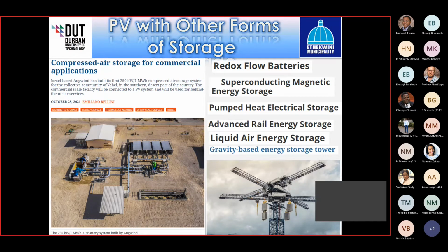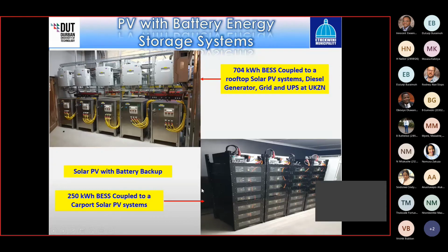And there are gravity-based energy storage towers, which use electricity to raise up weights. And when electricity is required, it then lowers these weights and generates electricity. So there are multiple energy storage forms and storage systems out there currently. They're still pretty new on the market, but I think the most common storage facility that's used with solar PV is battery storage systems. I've shown 2 examples here. These are systems installed in Durban. The top one, on the top left-hand side, is a 704 kilowatt hour battery energy system coupled to a 150 kilowatt rooftop solar PV system and a diesel generator.